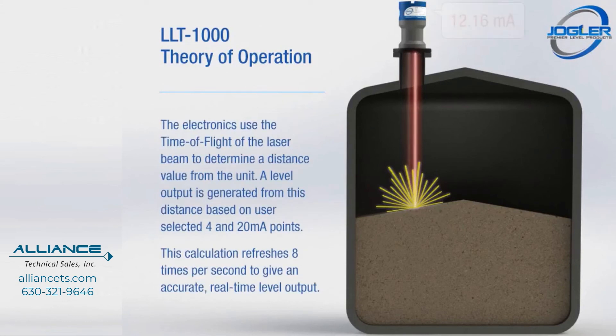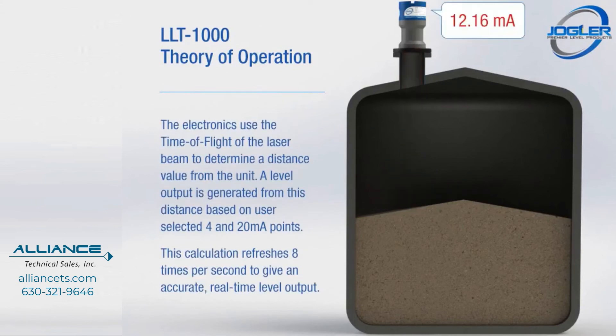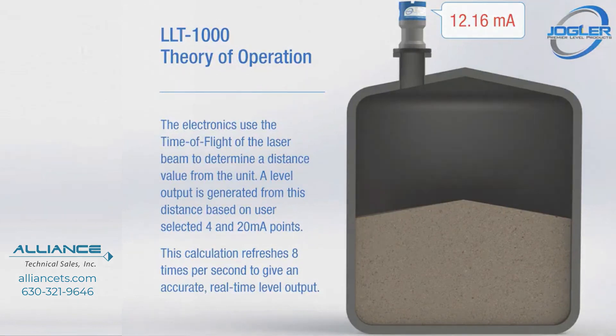The electronics use the time of flight of the laser beam to determine a distance value from the unit. A level output is generated from this distance based on user-selected 4 to 20 milliamp points. This calculation refreshes 8 times per second to give an accurate, real-time level output.